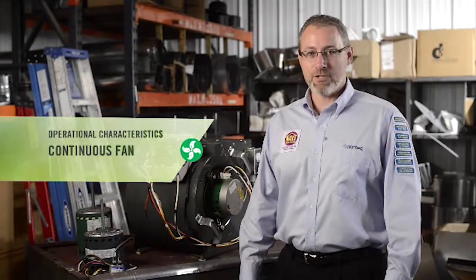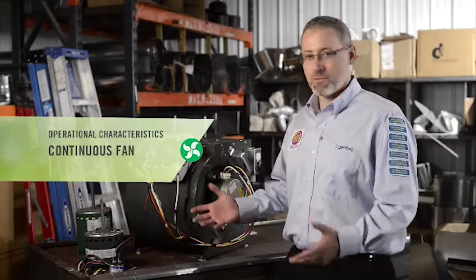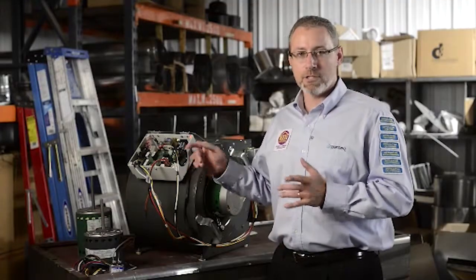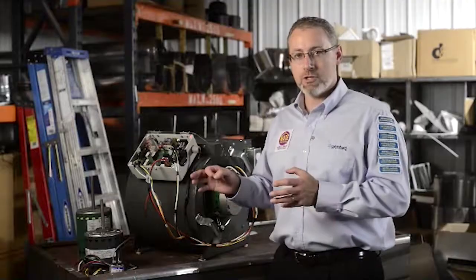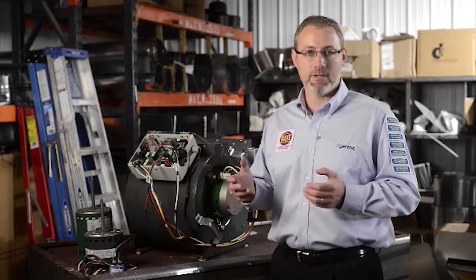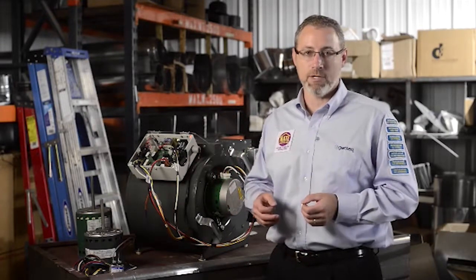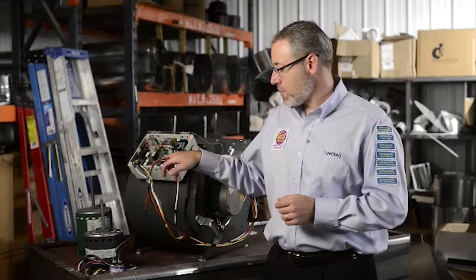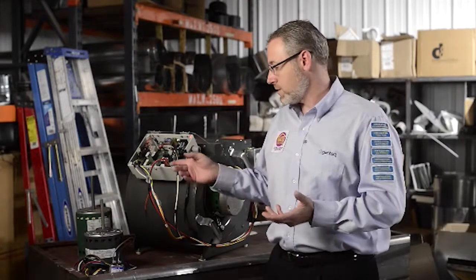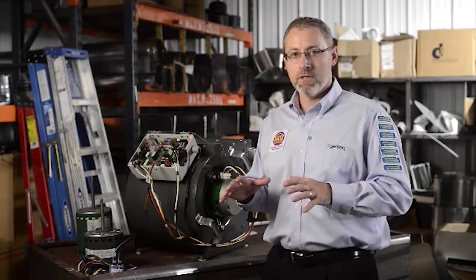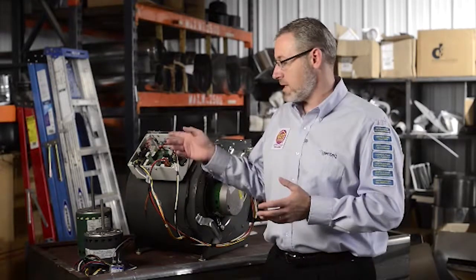The continuous fan operation is one more thing I like to talk about because, well, really it's one of the biggest features of the Evergreen IM. If you remember when we talked about connecting the thermostat wires to the speed taps of the Evergreen motor, we did not talk about connecting any speed taps from the motor to the G terminal on the board. The G terminal is what's energized when a thermostat is set to the continuous fan mode operation. The reason we don't suggest connecting any speed taps to G is that the horsepower wires, or what we call the high voltage signal wires, when they're energized alone, the motor knows to turn on. It just doesn't have a speed energized to associate with that on command.